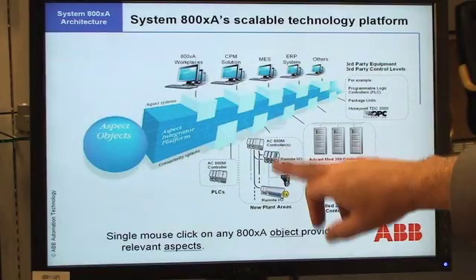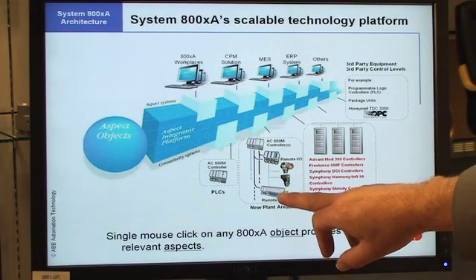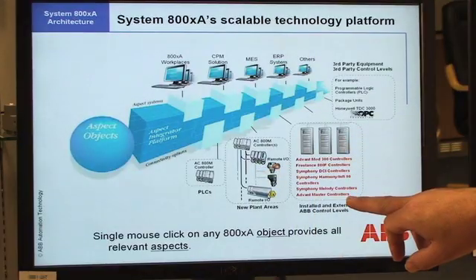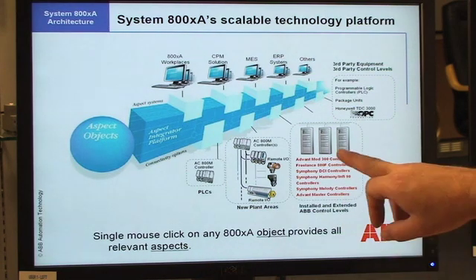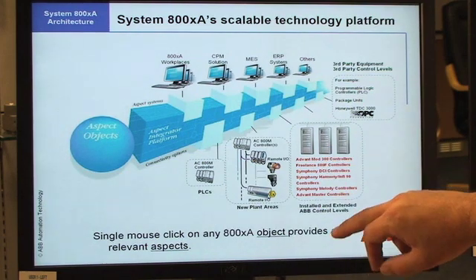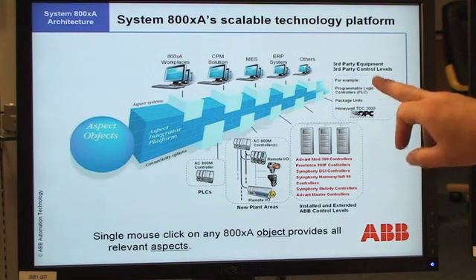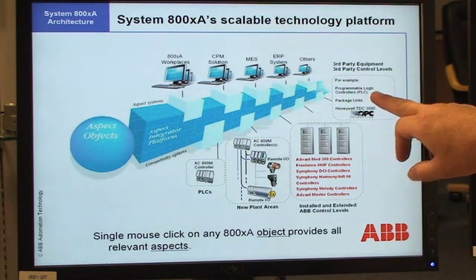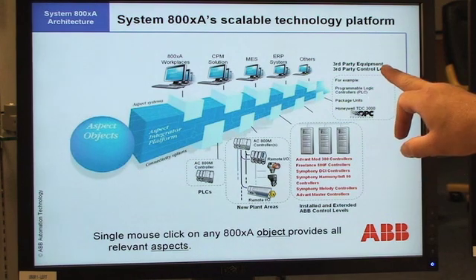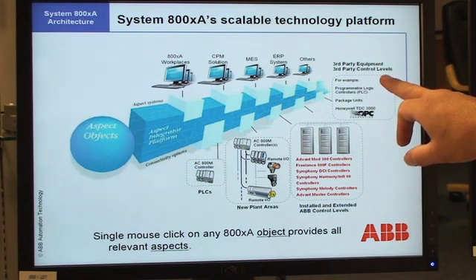If we want a full-blown DCS, we use the same 800M controllers, might use some remote I/O and some fieldbus, might add some drives, might add some more functionality. We can also link in the Evolution products from ABB — the Master, the MOD, the Freelance, the Symphony — and we also have OPC connections into all programmable logic controllers that have OPC using the PLC connector, so we can link into third-party equipment and controls quite easily.